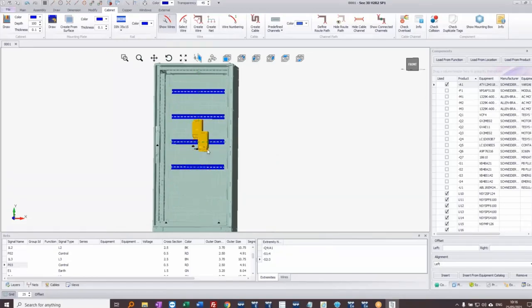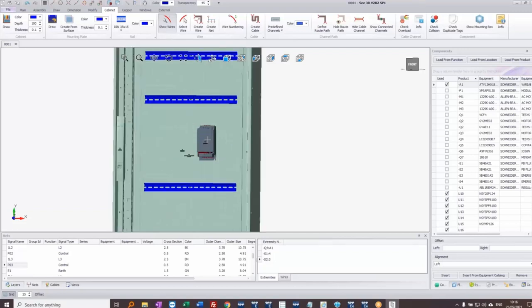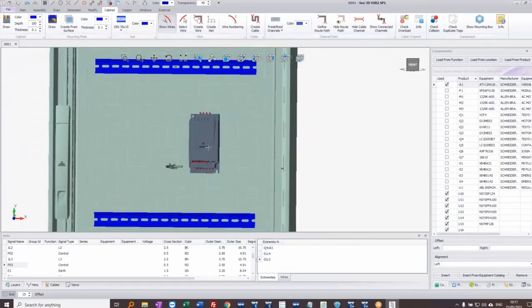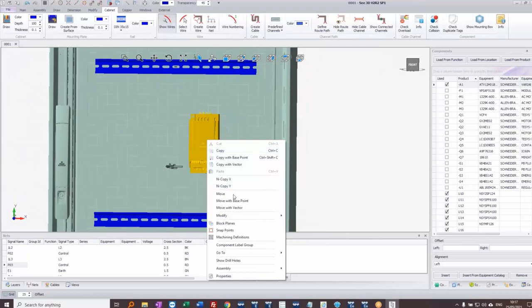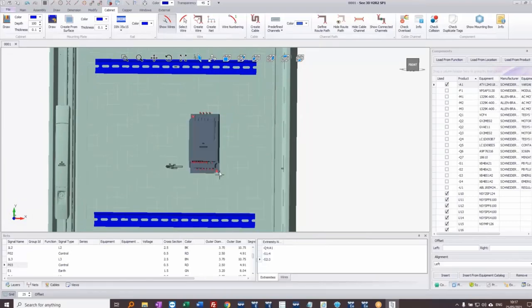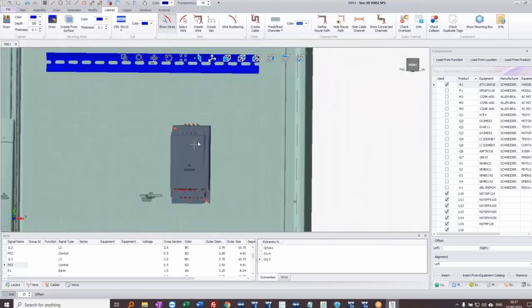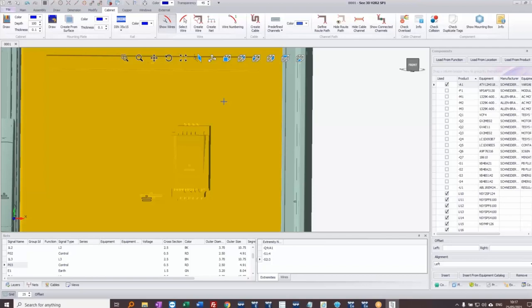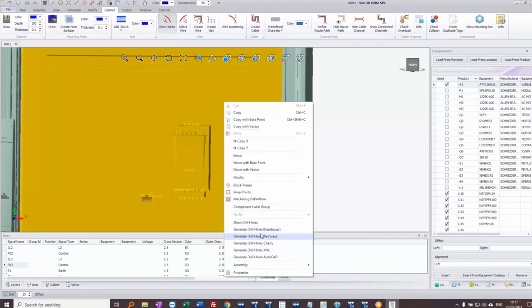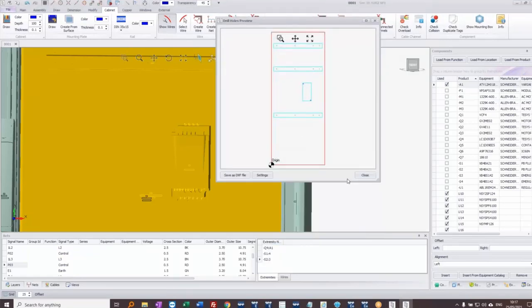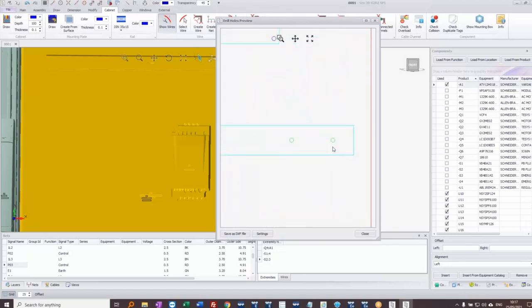I'll double-click to move the drive down and delete the one I don't need. Each device has the possibility of a drill template — right-clicking shows me the drill holes where they'll appear on the backplate. To check on the backplate itself, I right-click and choose to show the drill template, which would be sent to a CNC machine. I can see the outline of all components and the drill holes that will be added.